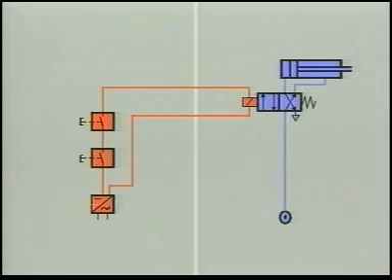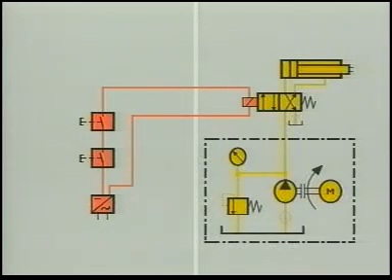actuated. In a corresponding electro-pneumatic control, there are electrical signal elements in the control part. In this case, signal processing is not carried out by a special device, but by connection of the various signal elements in such a way as to produce the function. The directional control valve, or more accurately, the solenoid valve, is now actuated electrically. This type of control part can, of course, also be used to control a hydraulic power part. Then we have an electro-hydraulic control.